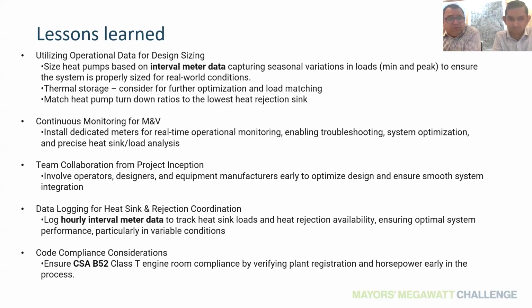Another consideration is to ensure that your engine room, like the refrigeration room, is code compliant. Once you start upgrading and attaching items to your system, since this building is a bit older, there are new exit and ventilation requirements. Even if they're not part of your original design, those should be implemented and be part of your project.